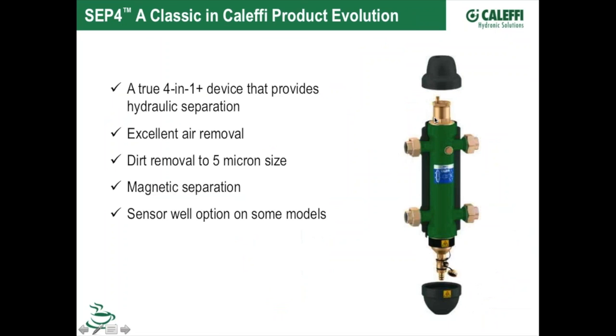We can put the same type of coalescing media inside there to do an excellent job of air removal. We can do the same thing at the bottom and do excellent dirt removal. We've added the magnetic band to it. So now we call this a 4-in-1 device: hydraulic separation, air removal, dirt removal, and magnetic separation. I'd even throw out there that it could be called a 5-in-1 device, because we also give you this little port right here, and you can put a sensor well in there, and you could use that as the operating point where the sensor from your boiler goes.